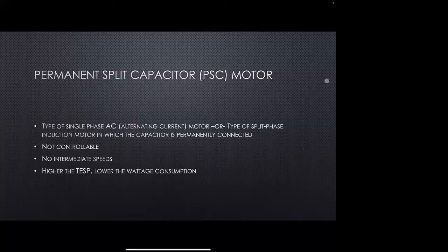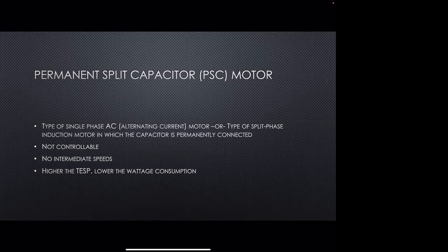Why is that? Because the higher the TESP on a PSC motor, the CFM output becomes less. When the CFM output is less, the RPM is less, which means the wattage consumption is less.